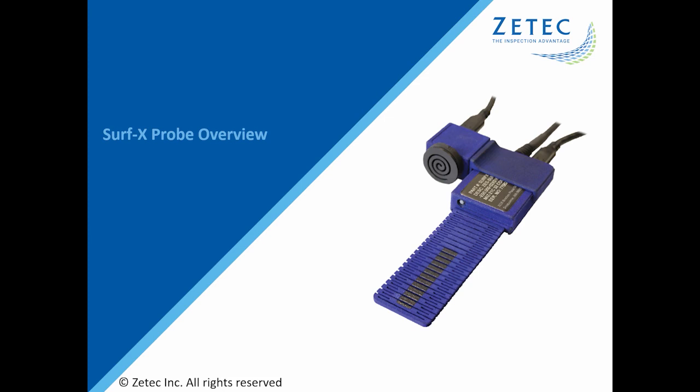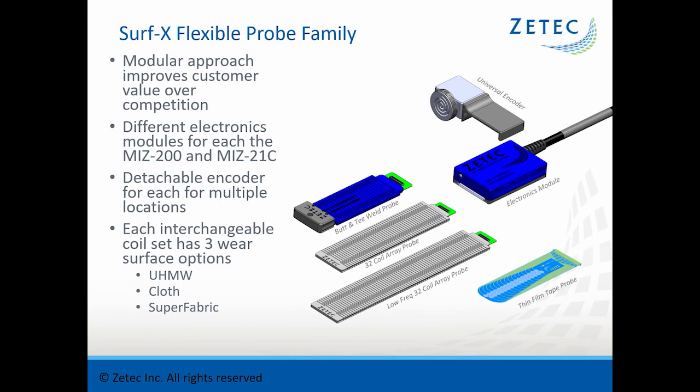This is Bill Ziegenhagen, probe product manager for Zetec. Today I'm going to be talking about an exciting new family of flexible surface array probes called the Surf-X Flexible Probe Line. What makes this probe line unique is its modular approach — the same items can be used to do a wide range of applications. Each probe comes with an electronics module to which you can attach different types of coil sets for different applications. The electronics module can also have a universal encoder attached in different positions and on either side of the probe.